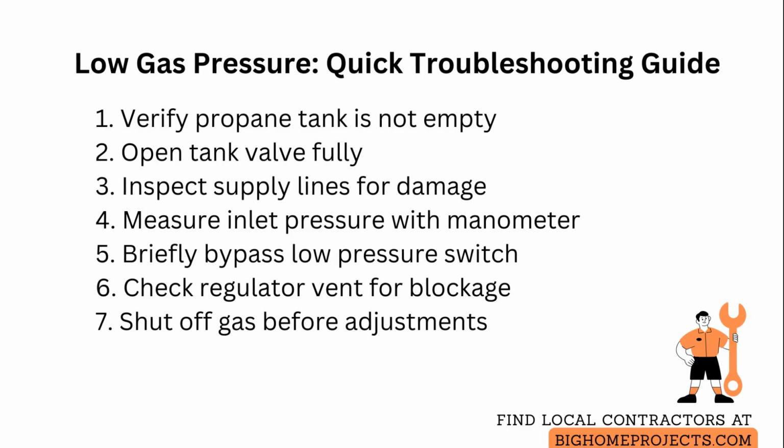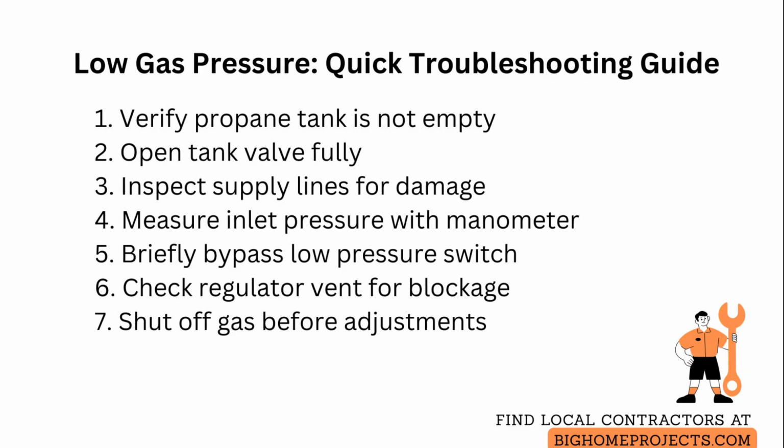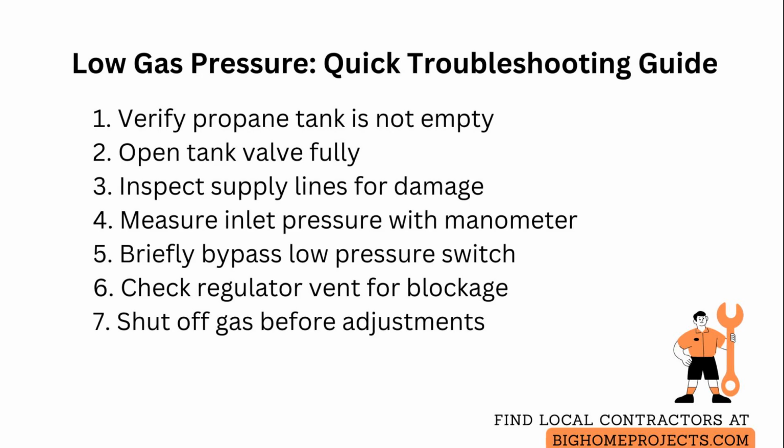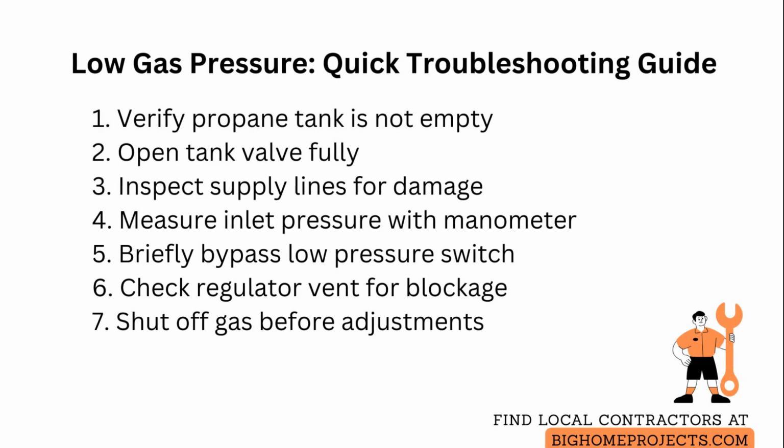First, verify the propane tank is not empty and that the tank valve is fully open, then visually inspect supply lines and fittings for obvious kinks or damage that could restrict flow. Use a manometer or the appliance pressure tap to measure inlet pressure against the manufacturer specification and compare at idle and under load to spot pressure drop under demand.